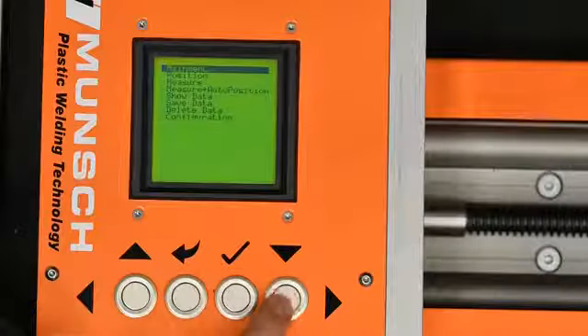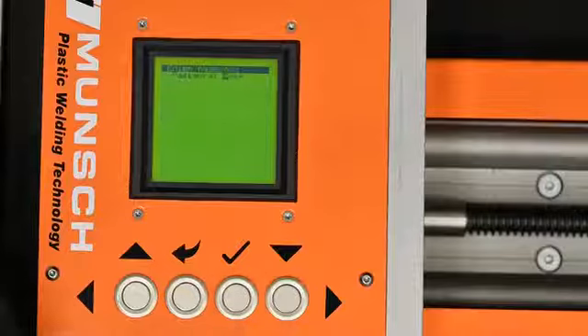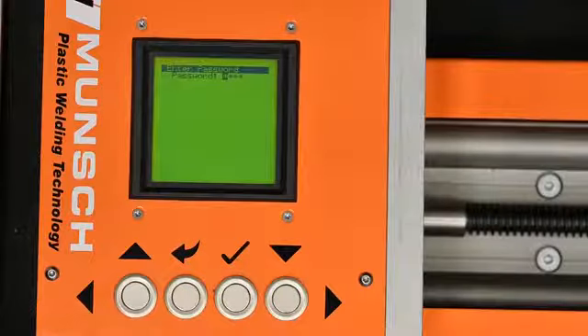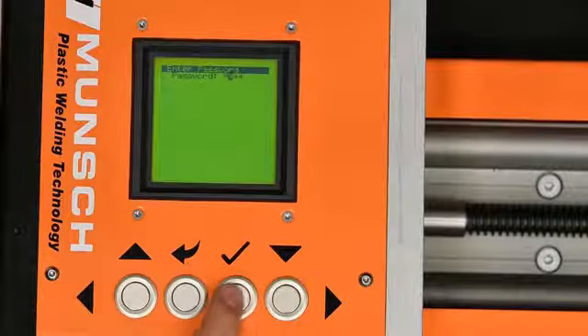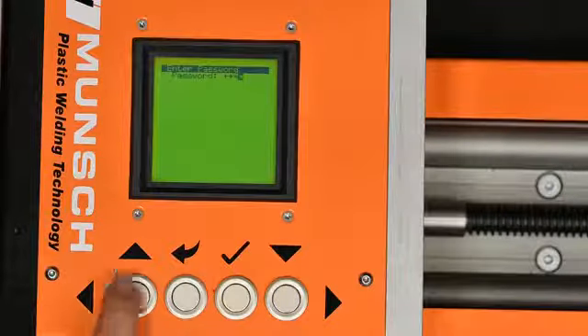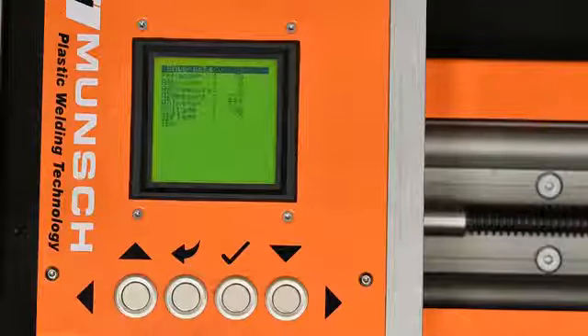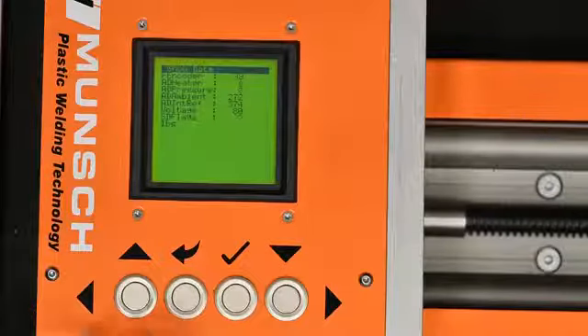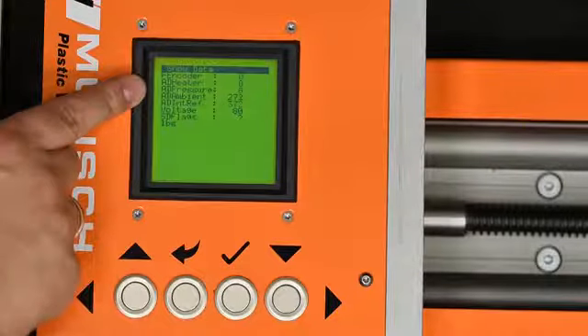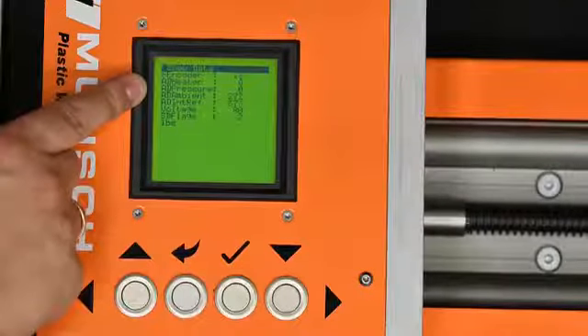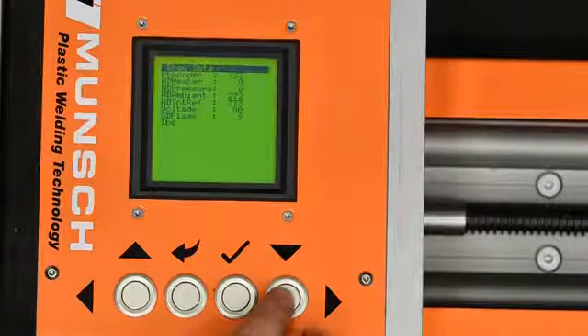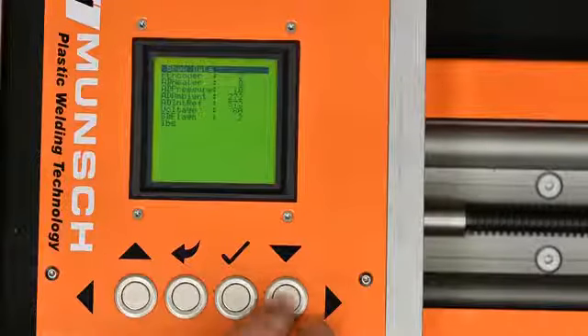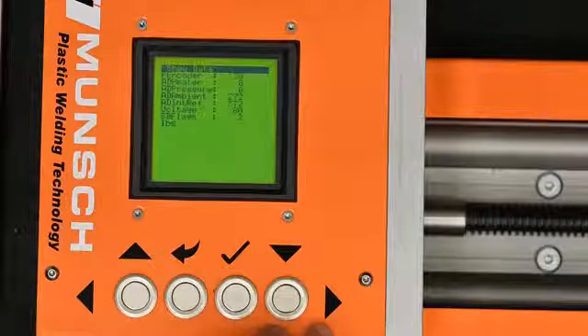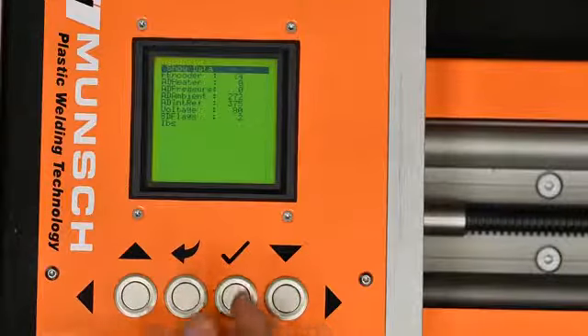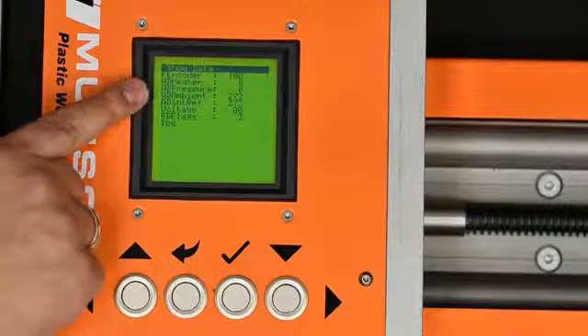You can calibrate the 0 point of the force. Therefore, please position the slider at least 50 mm from the ends of the slide. Then select Configuration in the main menu and enter the password 1001. In case the value AD pressure is not 0, lower it step by step with the down button until it constantly stays at 0. Then exit by pushing Return.